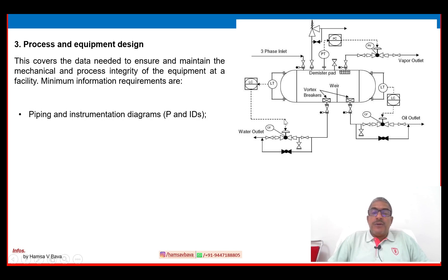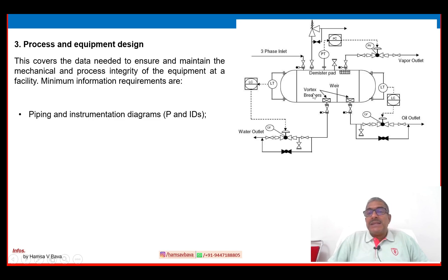In the P&ID, the difference from a PFD is that it shows most of the instruments — such as level transmitter, level controller, level control valve, LT, LC, pressure transmitter, pressure controller, and pressure control valve. It also shows internals of separators, pipeline dimensions, pipeline details, and various instrument and electronic signals — providing much more detail. Please read the P&ID module available separately to get that information very well.